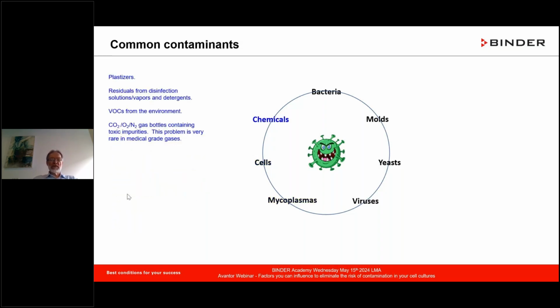Chemicals, most of you probably won't be thinking of chemicals as a severe contaminant, but if you think of the plasticizers, for example, or residuals from a wipe disinfection, many of you use 70% alcohol, others use disinfectants, detergents. If that is not wiped down correctly, then you have residual vapors inside, and that also contributes to bad cell growth. VOCs from the environment. I can remember a time when I was heavily involved in IVF, in vitro fertilization. Here we encountered many cases where formaldehyde-containing soaps located on a sink in the vicinity of a CO2 incubator had a negative influence on the success rate. And things like that must be taken into consideration.